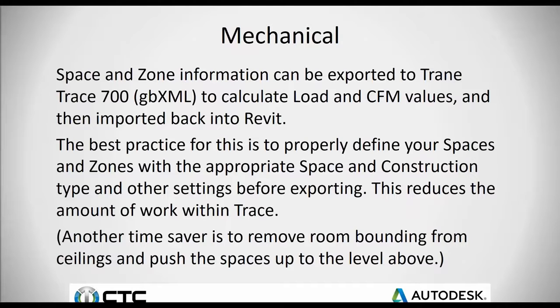We can also take our space and zone information and export that to Trane Trace 700 or as a gbXML. There's any number of load calculation software out there, but to my knowledge, Trace is the only one that will bring those numbers back into Revit and populate your calculated values.